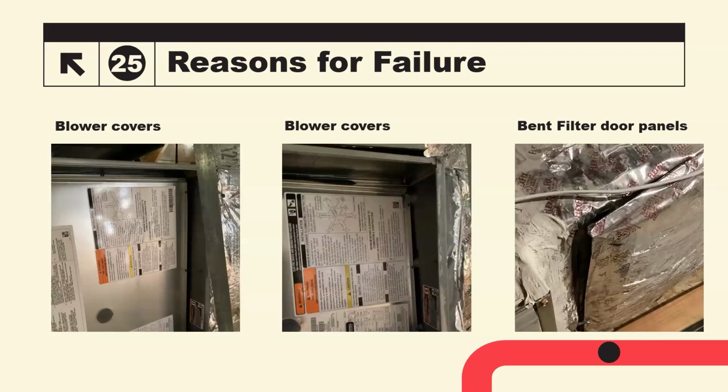Now, you could do a diagnostic and say, well, I taped all this stuff up, and it passed when I taped it up. But you need to take the tape off, fail it, and then have them fix this so it's actually going to pass with these doors being sealed shut. You won't have to do the test again as long as you can verify that the door is sealed and fixed at final. I know that most of the time it's probably not going to be.